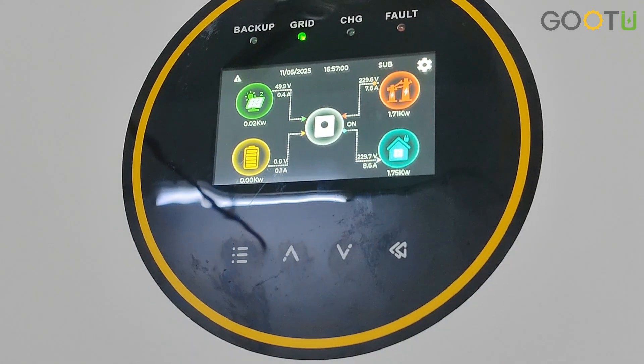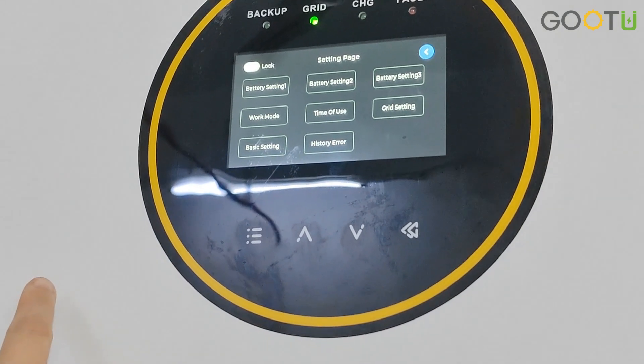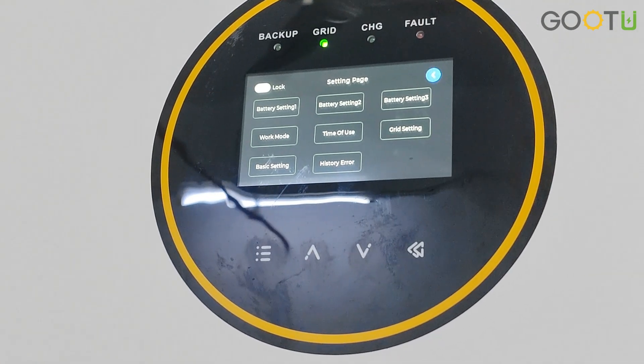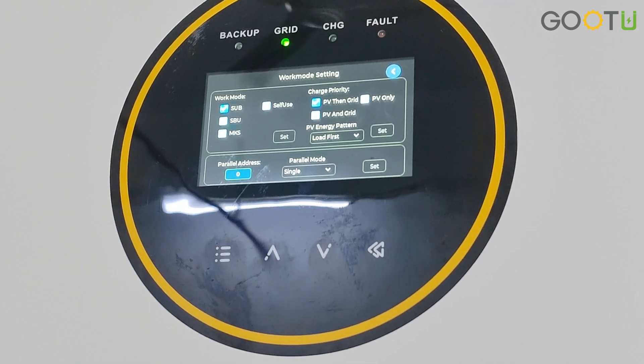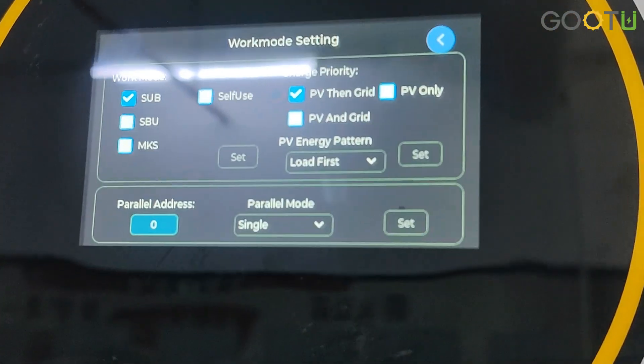You can set all the details according to our user manual from the settings page. This has battery setting, work mode, time of use, grid setting, and basic setting. For the work mode, you can set from 0 to 1. The modes available are SUB — solar first, utility second, battery third — SBU, MKS, and self-use.